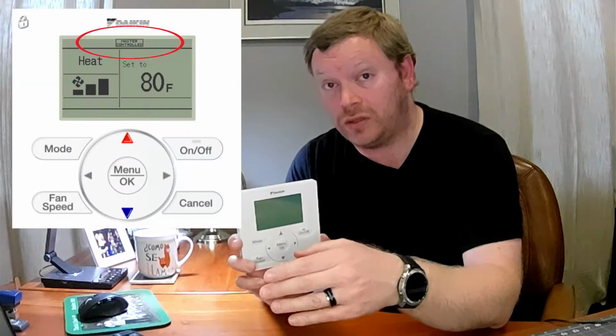If you look at a VRV application and you have all NAV controllers connected, one to each indoor unit, it's actually really easy. One of these units is going to be set up as the master during the installation process by the technician, and you know which controller is the master because at the top there's no icon, it's blank at the top. All of the other NAV controllers are going to have an icon at the top that says master controlled. They're telling you, hey, we're not the master, we're being master controlled. So you know then you need to find the NAV controller at your house that's blank at the top, because that's the only controller that can choose the mode of operation of the heat pump system. All the other NAV controllers can pick their own set points, their own fan speeds, on off. It's just the mode that gets picked by the main master controller.